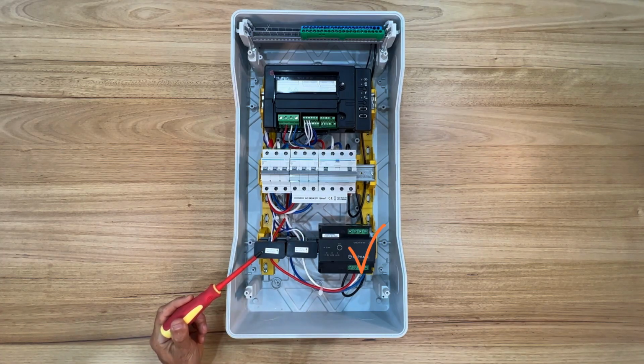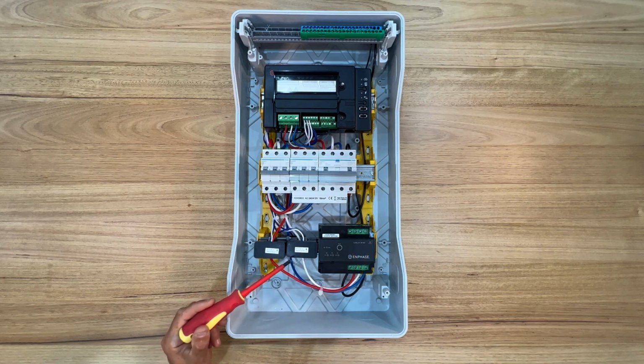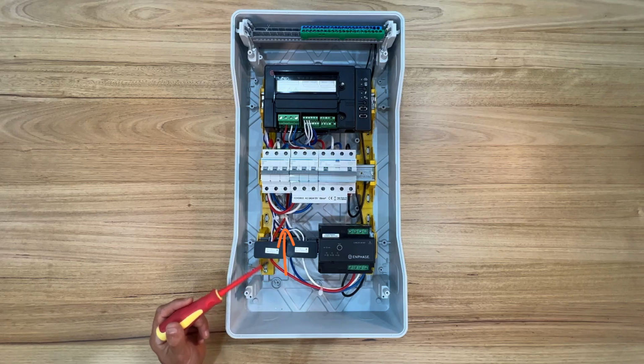A current transformer, or CT, must be attached around each of the solar phases. Now each CT has a direction arrow. The direction arrow follows the current. So for this example, the arrow must face away from the solar back towards the circuit breaker or RCBO.